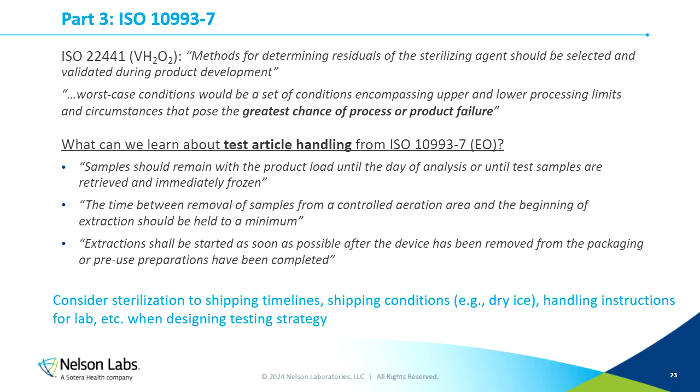Now, the spirit of all of these terms to me is that the time between sterilizing the device and putting it through this testing to extract the amount of residues should be held to a minimum.